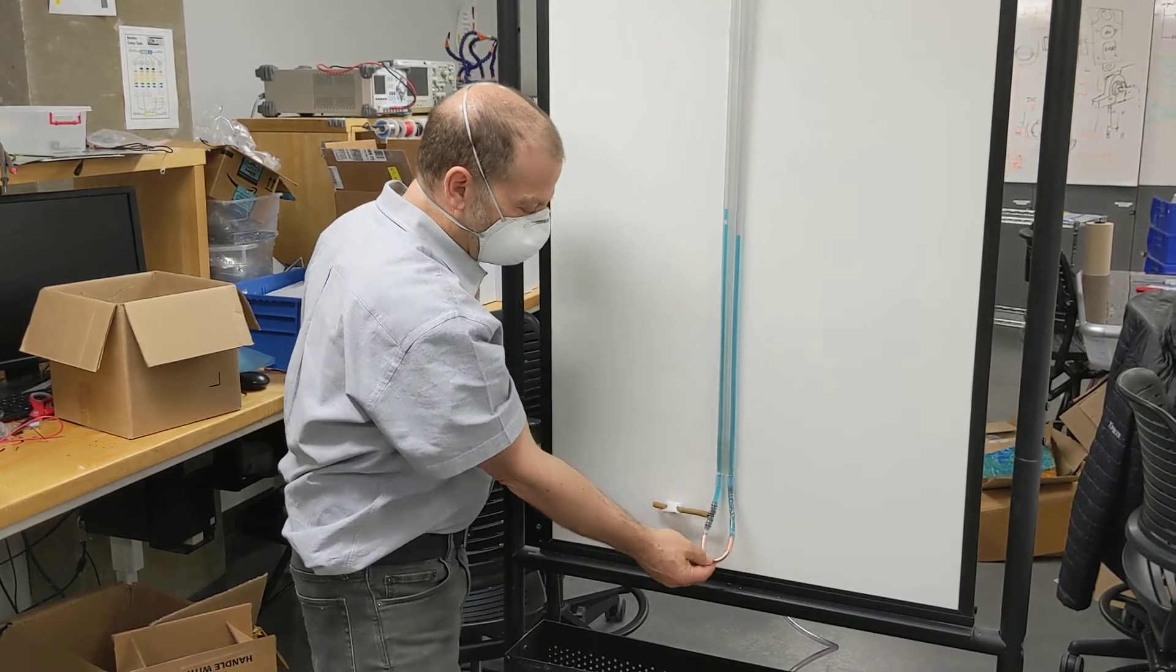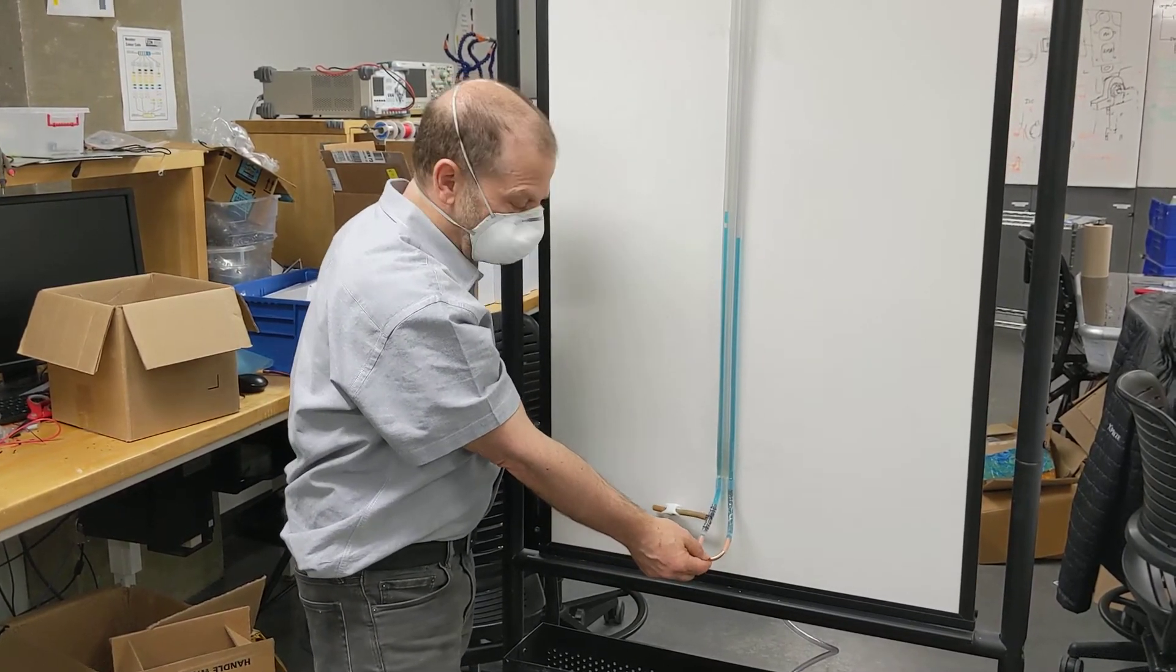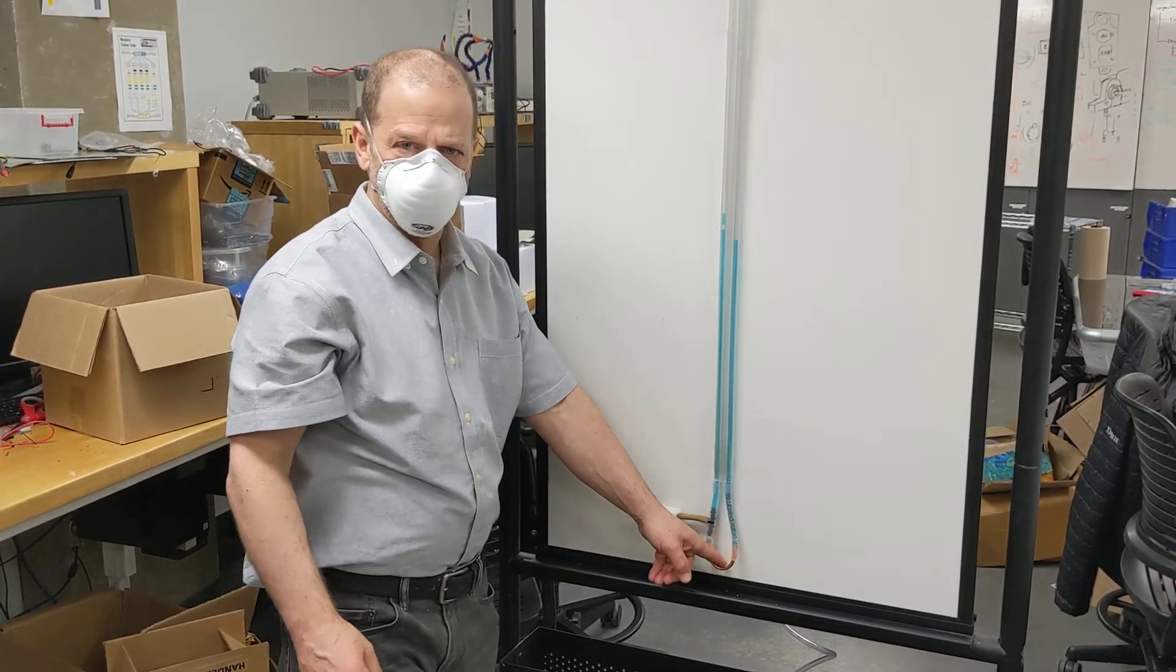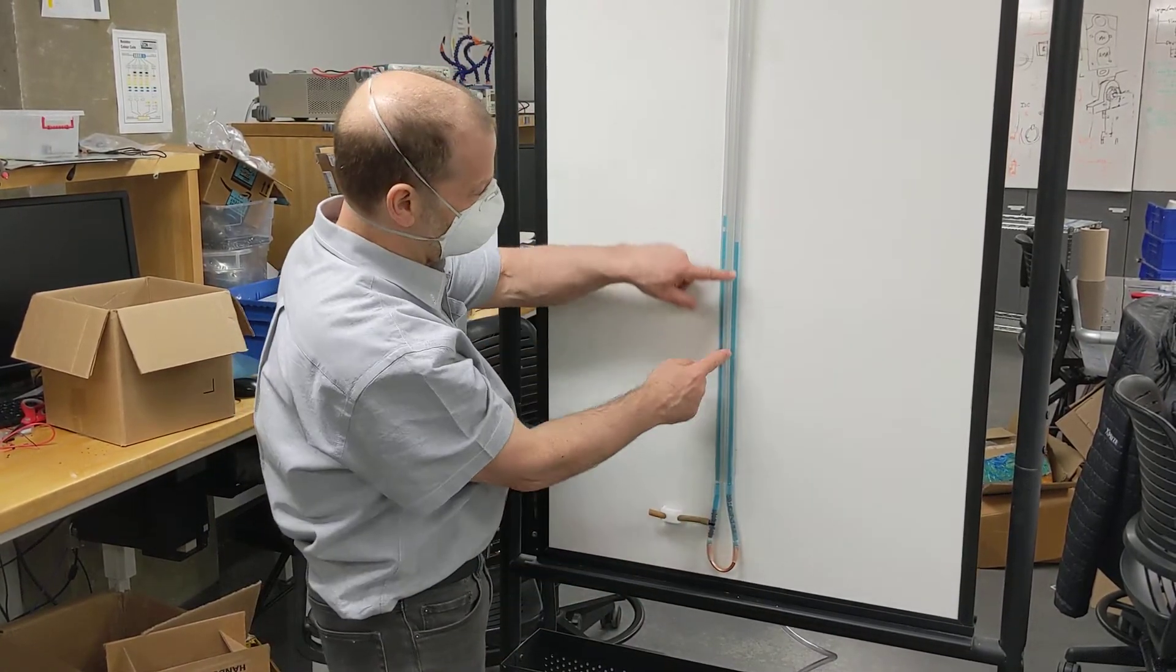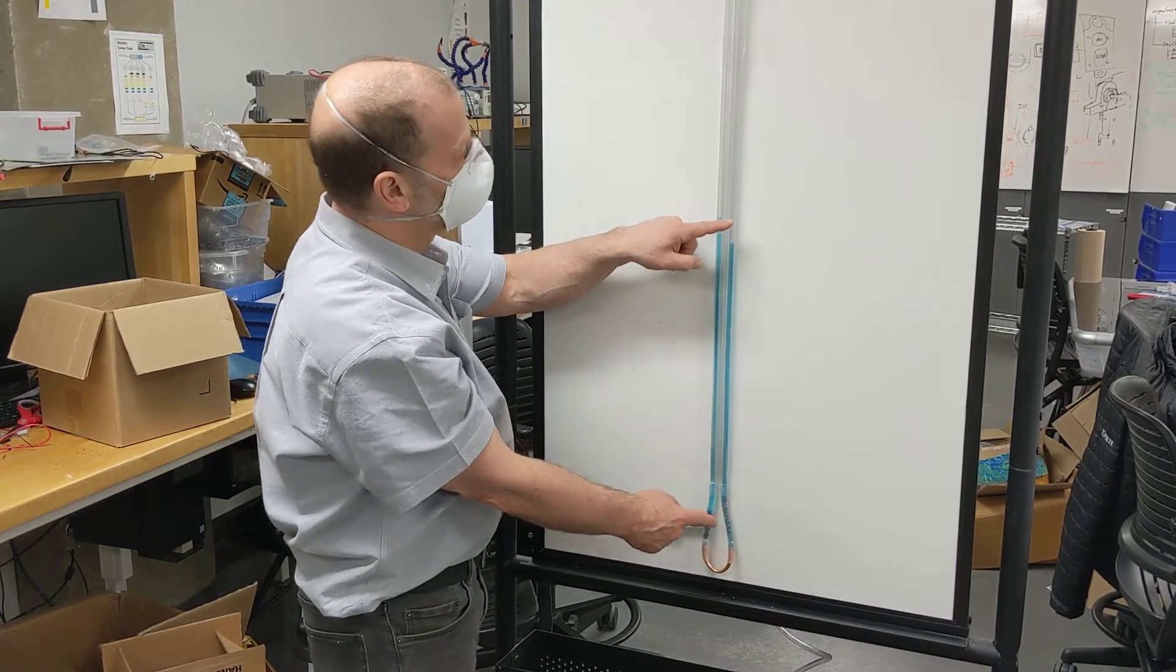We're going to use that for an electrical connection too, because this is used for making the overpressure alarm through electrical conductivity through the lightly salted water to one of these arms.